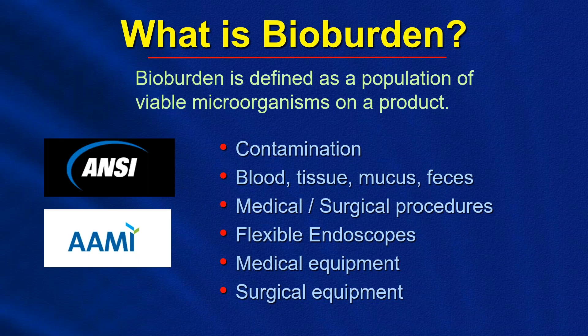Now, this gross contamination, if left on surfaces or in scopes and instruments for too long, may allow for the formation of biofilm. Now, what is biofilm? Well, biofilm is defined as an aggregate of microbes in which cells adhere to each other and or to a surface, producing a distinct architecture. Biofilm can form as the result of bioburden not being removed quickly and efficiently and allowed to start drying. These microbes will adhere to a surface. They'll begin to build a matrix that holds the biofilm community together, and then the microbes will encase themselves under a protective polysaccharide layer. Nutrients will start to feed the biofilm community and allow them to proliferate and grow.